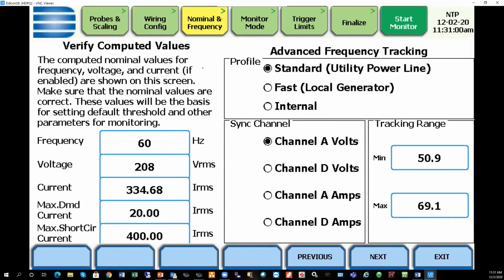And again, especially if you're doing TDD, because TDD is based on a ratio of what we call the short circuit current here to the max demand current. Now, the short circuit current is usually provided by the utility. If you don't already know the max demand current, how it's usually calculated is you take the peak demand current over 12 consecutive months and you determine the average. By putting these two key pieces of information in, the instrument knows what is called the short circuit to demand current ratio, and that is key as far as making sure that you have the limits selected.